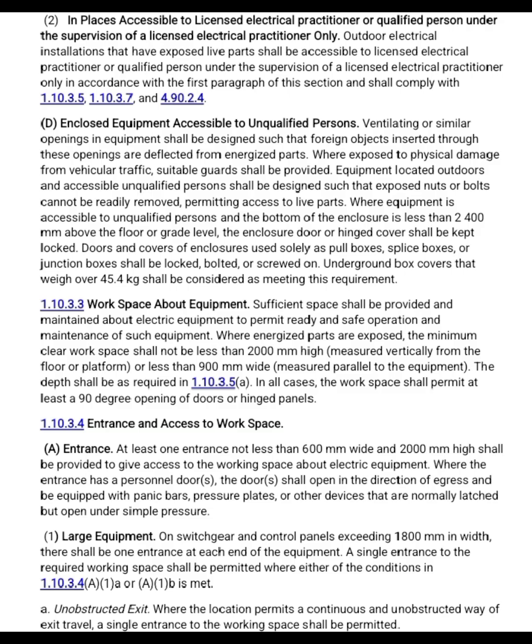1.10.3.4 Entrance and access to workspace. A. Entrance. At least one entrance not less than 600 mm wide and 2000 mm high shall be provided to give access to the working space about electric equipment. Where the entrance has a personnel door, the door shall open in the direction of egress and be equipped with panic bars, pressure plates, or other devices that are normally latched but open under simple pressure.